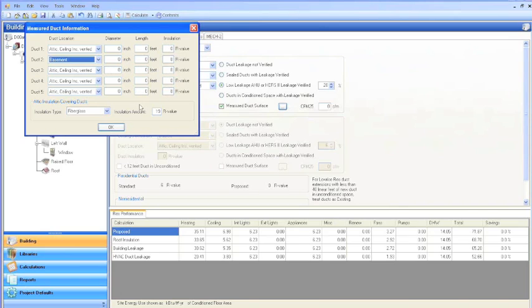What we didn't want to do is insist everybody do this, because there's apt to be different diameters as you go through the whole network, and Energy Pro only allows 5 runs to be here. So if you are breaking out the parts of your duct system, do what you can to group things together. Energy Pro is more concerned about diameter, length, and insulation levels, and it's not so much concerned about proximity, say, to the air conditioner, how far away it is. It's making some average assumptions about that. So you can generalize this to the nature of the ductwork in the attic versus the basement, say.